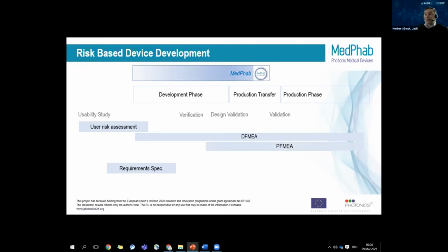Next to the design, I have my PFMEA, a process risk assessment, if you like, and a supplier risk assessment. With these instruments, which again can be kept on a reasonable level, I can achieve a closed loop process that later in the production phase will allow me to maintain my product.